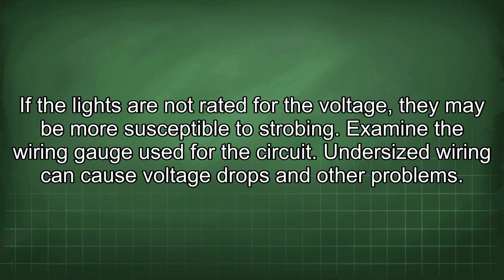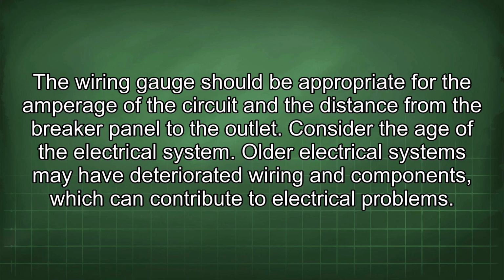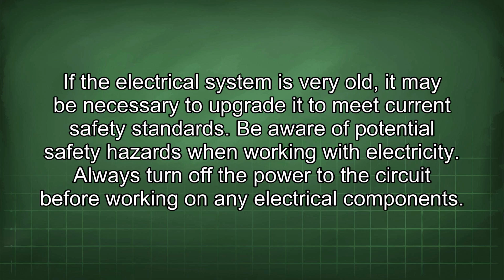Undersized wiring can cause voltage drops and other problems. The wiring gauge should be appropriate for the amperage of the circuit and the distance from the breaker panel to the outlet. Consider the age of the electrical system. Older electrical systems may have deteriorated wiring and components, which can contribute to electrical problems. If the electrical system is very old, it may be necessary to upgrade it to meet current safety standards.